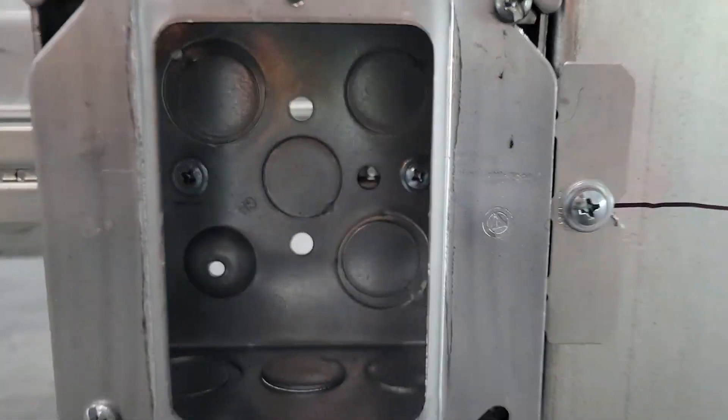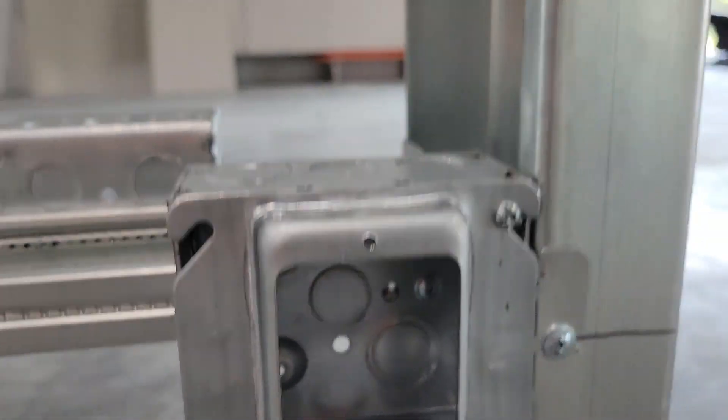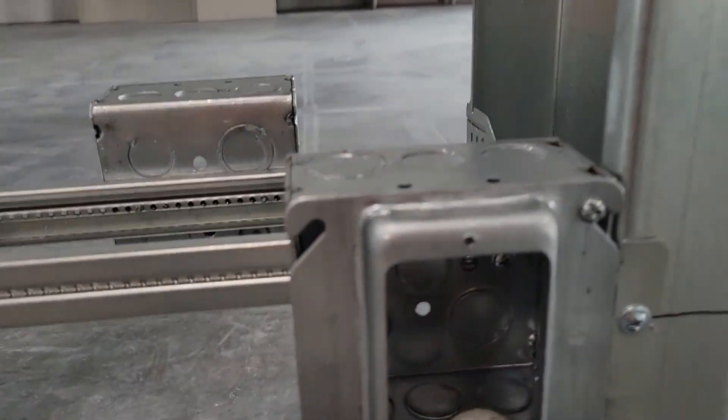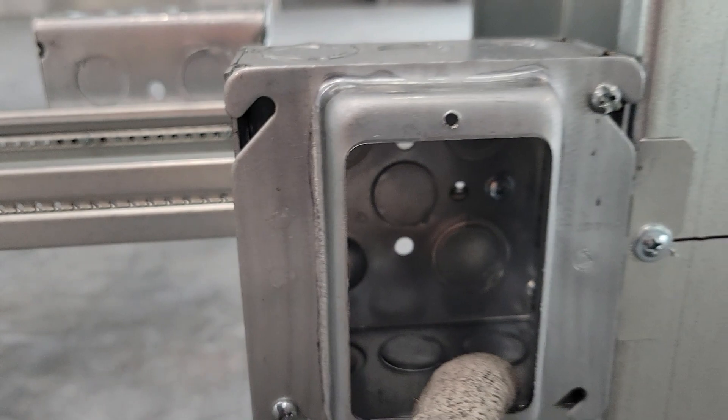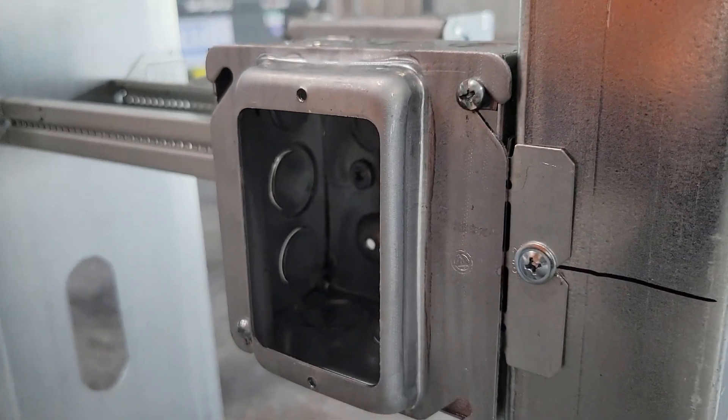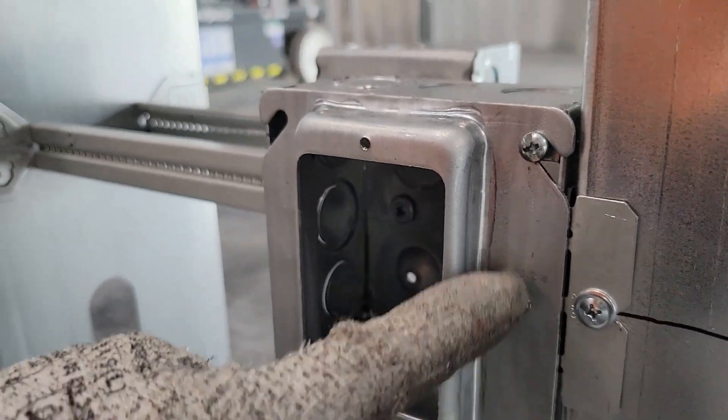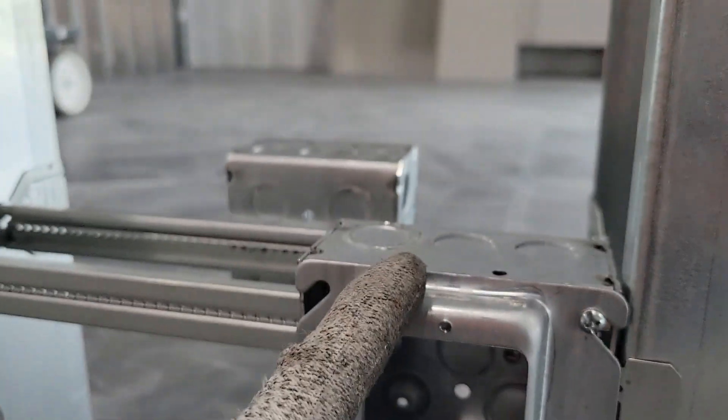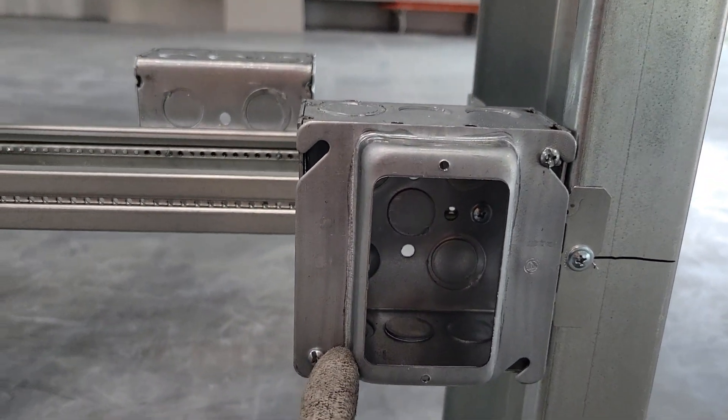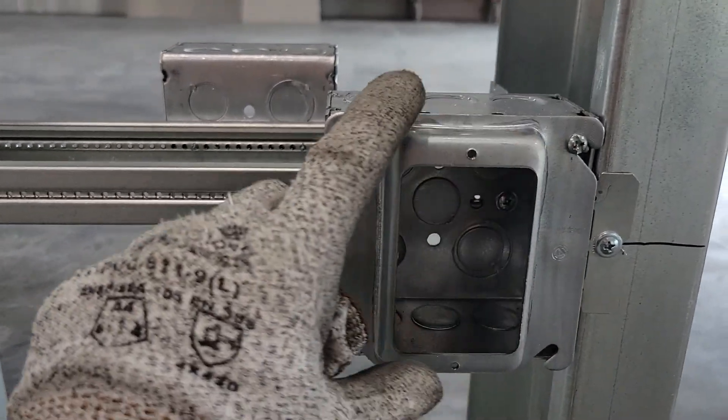After you put your box on, you put what's called a mud ring. This mud ring is flush with the wall and sticks out the distance of five-eighths drywall, so that way when they put drywall on, they can just zip around this.